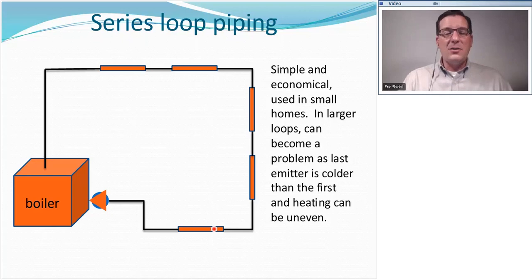So be aware, those are some of the problems that we experience with series loop because of that temperature difference. As the water passes through the different emitters, the last one kind of gets the short end of the stick, essentially. By the way, I want to mention, this symbol here means pump. When you see a circle with a triangle in the middle of it, that is the universal symbol for circulator pump. And the pump usually points, the triangle usually points in the direction of water flow. So here we have water in here, water out there.